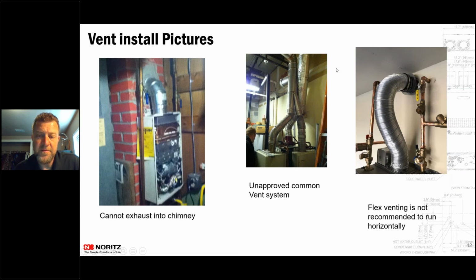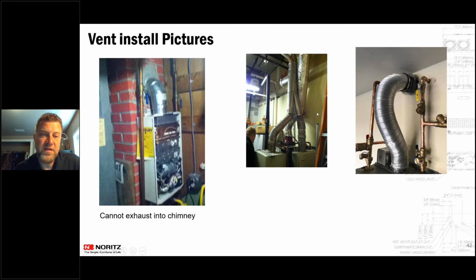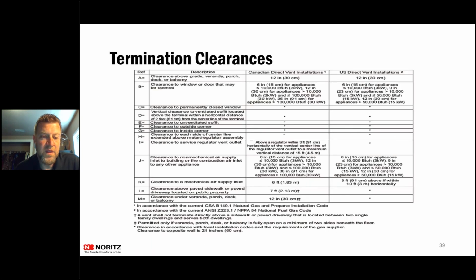Hey, Gail? Yeah. What about venting underneath a deck? So in the National Fuel Gas Code, for the clearance under a veranda, porch, deck, or balcony, there is no clearance there. I've seen a ton of those installs where they've vented under decks, but it's all up to the inspector's interpretation of their local code. We say we don't have a clearance on it, neither does the National Fuel Gas Code, but it is up to that local jurisdiction.